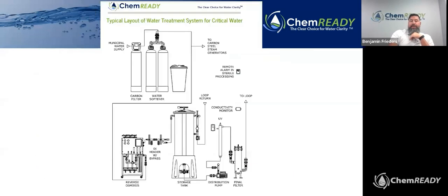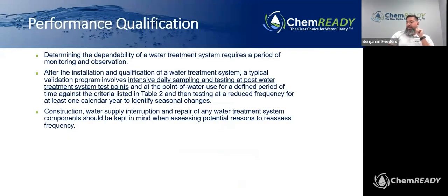Per the standard, what that means is if you come to a critical water system, it means that after each treatment step, carbon filter, water softener, reverse osmosis, DI, UV, and bacteria endotoxin testing, you require intensive daily testing against table 2, all of those ionic contaminants I showed you before, for a period of time, and then at a reduced frequency for a year. What does that mean in practical terms? You're talking $50,000 to $100,000 in laboratory testing. It's a pretty big step up, right? From having to do nothing to having to be compliant with the system.